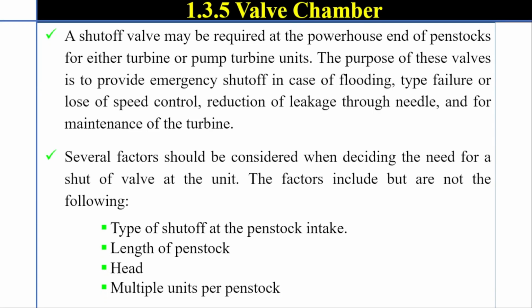Valve chamber. A shut-off valve may be required at the powerhouse end of penstocks for either turbine or pump turbine units. The purpose of these valves is to provide emergency shut-off in case of flooding, pipe failure, or loss of speed control, reduction of leakage through needle valves, and for maintenance of the turbine.